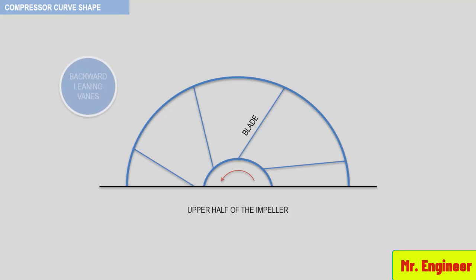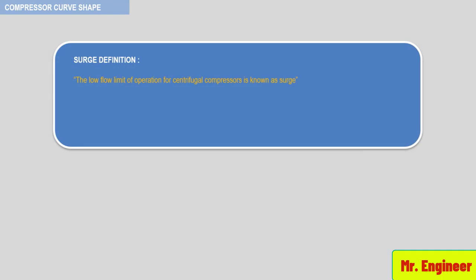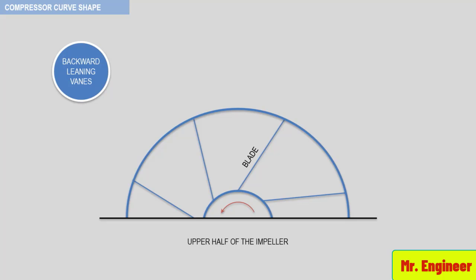The previous discussion was focused on the characteristic of a backward-leaning vane impeller. Most centrifugal compressor vanes are backward-leaning, since they produce a greater head rise from the impeller design point to the low flow operating point. The low flow limit of operation for centrifugal compressors is known as surge. Head rise is defined as the head produced at the low flow operating point divided by the head at the impeller design point. The industry prefers backward-leaning impellers with an exit blade angle of approximately 40 to 50 degrees, producing head rises in the range of 5 to 15 percent depending on the gas density.